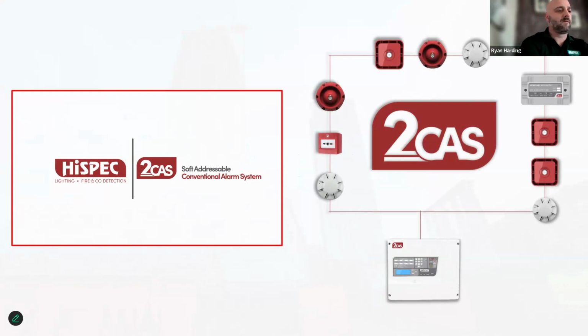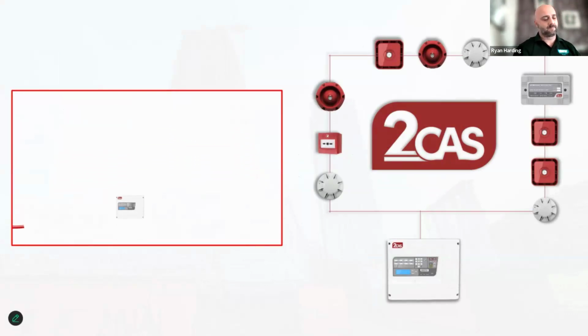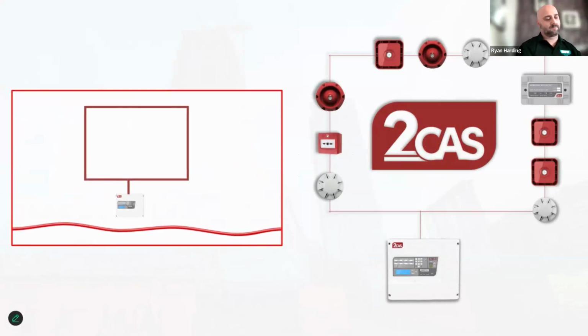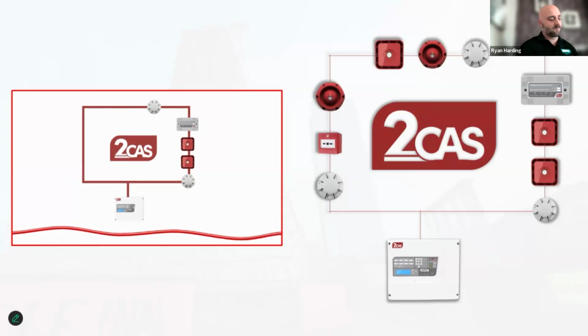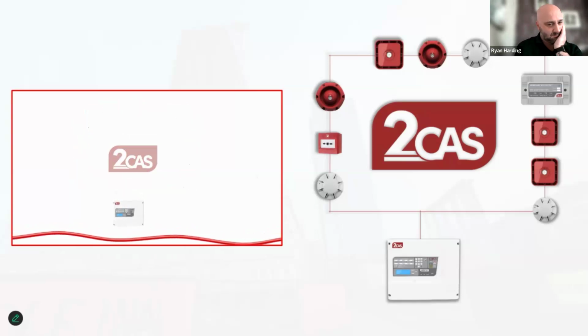Introducing the new commercial fire alarm system from Hispec, 2CAS, the 2-wire conventional alarm system. The 2CAS panel is a single-loop 2-wire conventional alarm panel with the ability to soft address devices in smaller installations. 2CAS uses MK2 protocol, so can run any of our addressable devices. Detectors, call points, interfaces and sounders can all be connected to the same addressable loop.